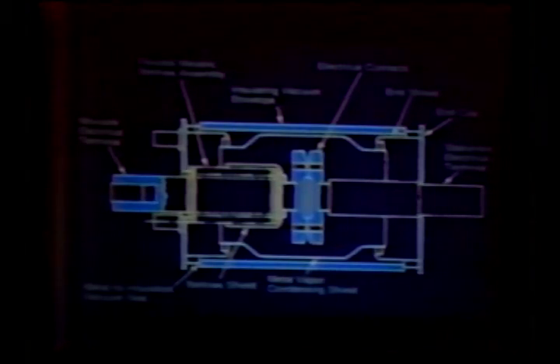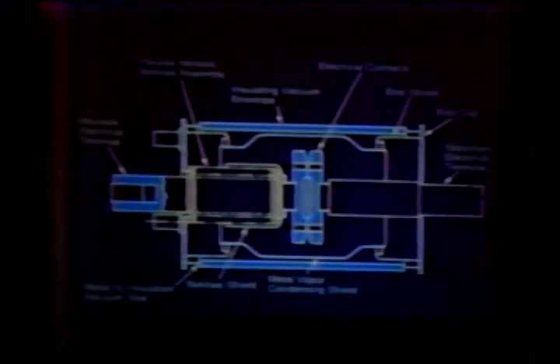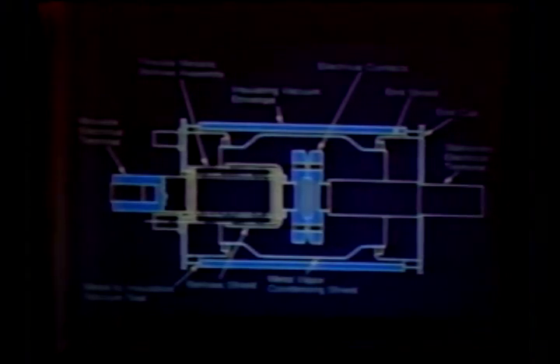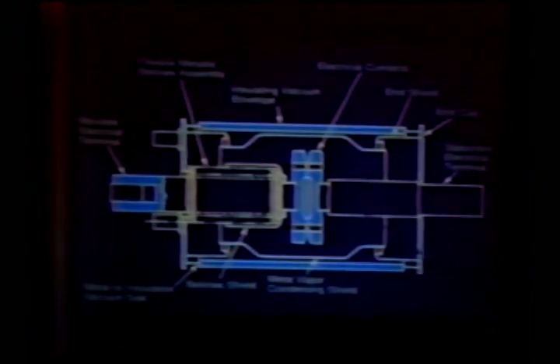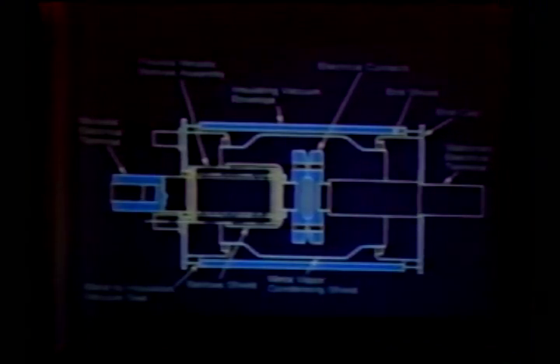The vapor condensation shield is included to protect the insulating vacuum envelope from vapor deposition during arcing cycles. The high voltages are withstood by the vacuum condition and the ceramic envelope internally. Usually externally, you rely on the length of ceramic envelope exposed to air to withstand the high voltage transients. You have a fixed electrode and a bellows electrode, and we'll be talking about the typical strokes involved in operation of such a switch.